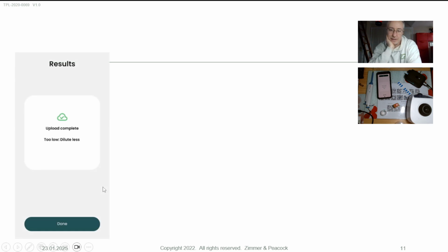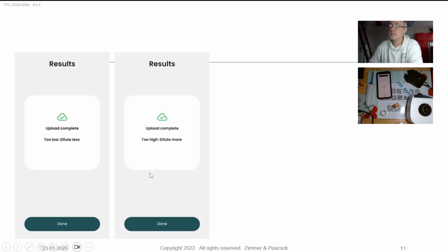Hi, welcome to this video, and this video is helping clients to troubleshoot. So a particular client has, first of all, an error message. Now, apparently it's the same sample, so this is a very unusual issue, because at one point they test the sample and it says upload complete, too low, dilute less. So this essentially says that this is a very low capsaicin concentration. And then it says upload complete, too high, dilute more.